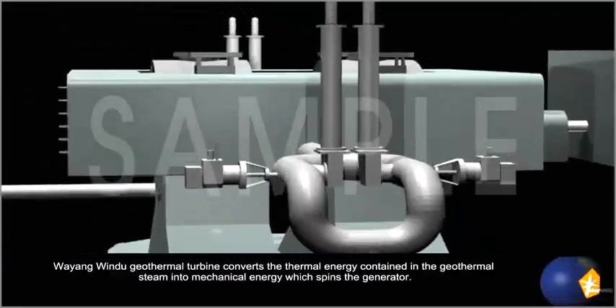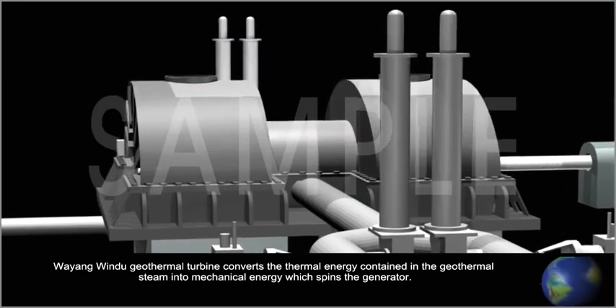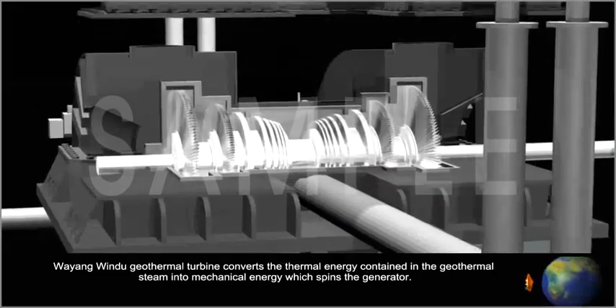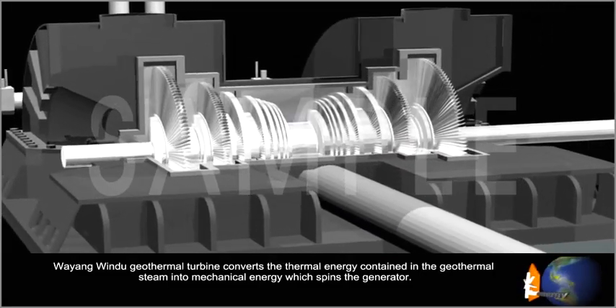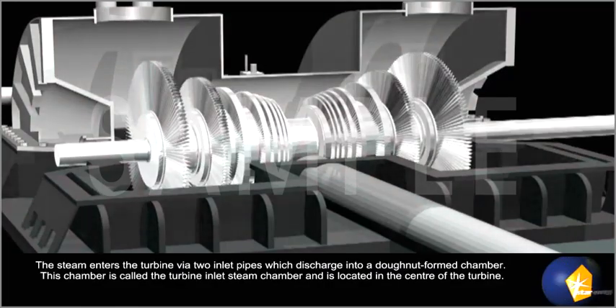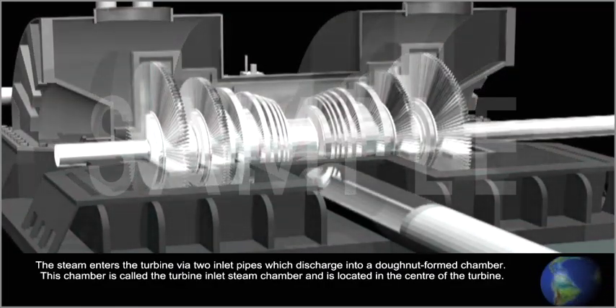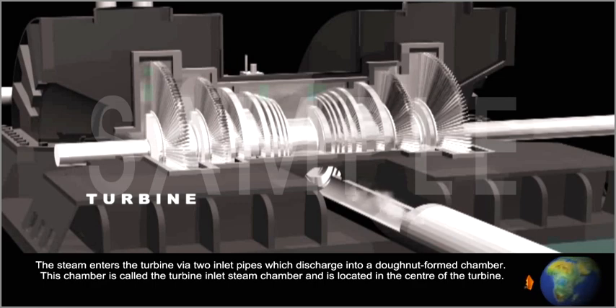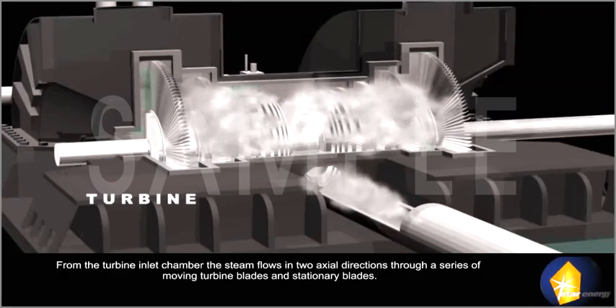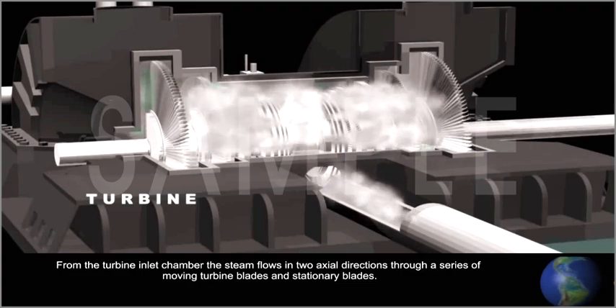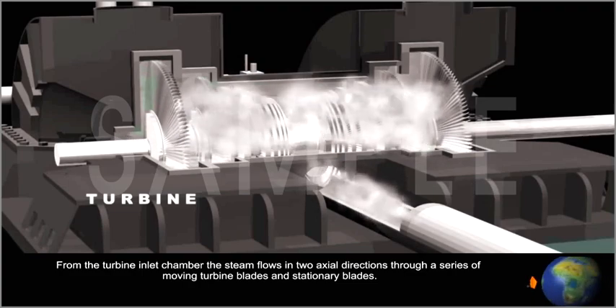Wayang Windu Geothermal turbine converts the thermal energy contained in the geothermal steam into mechanical energy which spins the generator. The steam enters the turbine via two inlet pipes which discharge into a donut-formed chamber. This chamber is called the turbine inlet steam chamber and is located in the center of the turbine.